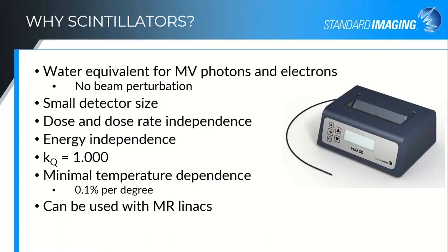Another advantage of scintillators is that there aren't any ferromagnetic materials within the detector itself. So with a long fiber, you can use it with an MR Linac as long as the electronics themselves stay outside the five gauss line.